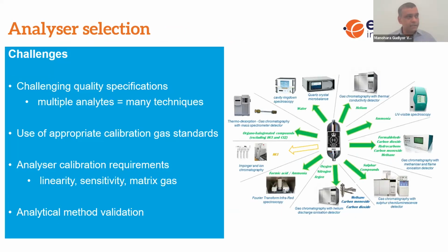So another difficult problem is selecting analyzers. We hear a lot of people saying this analyzer is better than that one, and that it does a good job. This is heard again and again from a lot of people. Everybody in this field is no exception. So we need to consider the number of analytes we need to analyze, whether one technique is enough or we need to consider many techniques, and the use of an appropriate calibration standard for that particular analyzer.